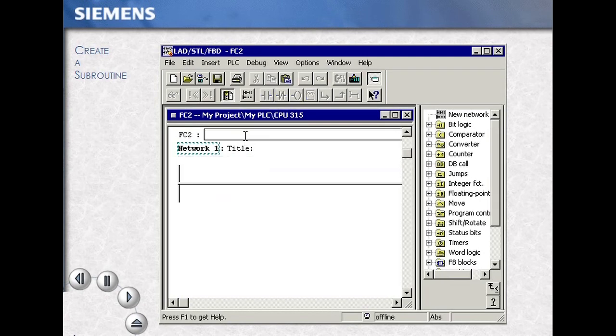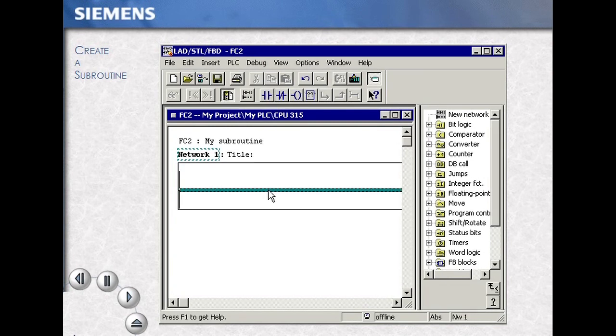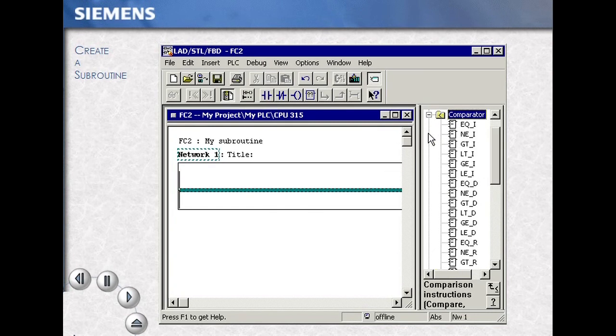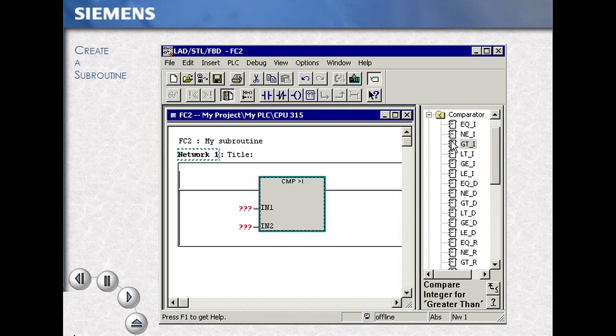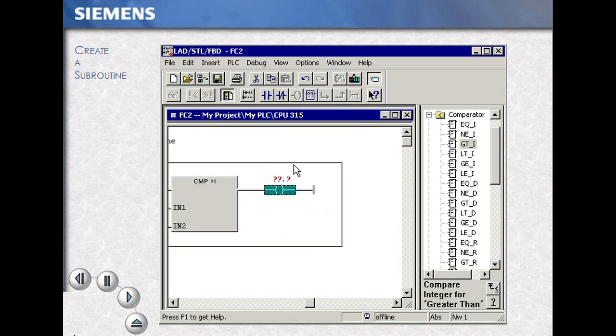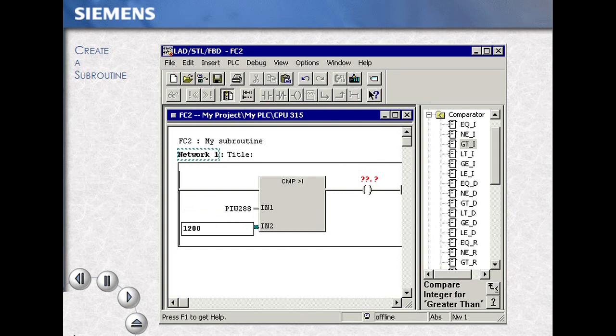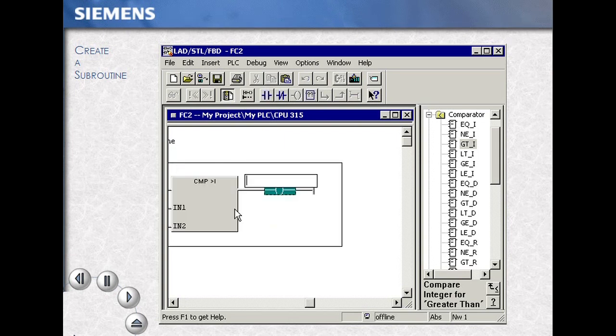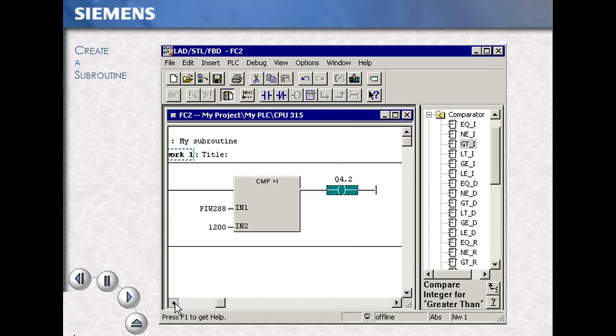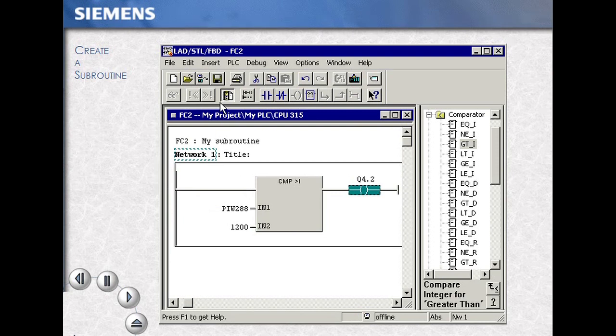We now do some basic programming and some basic documentation. Using the program elements, this example uses a greater than integer box to an output. Using the addresses PIW288, compared to the value of 1200, turning on Q4.2 output. Save your work using the save icon.